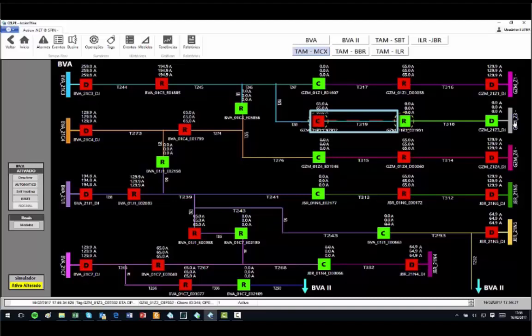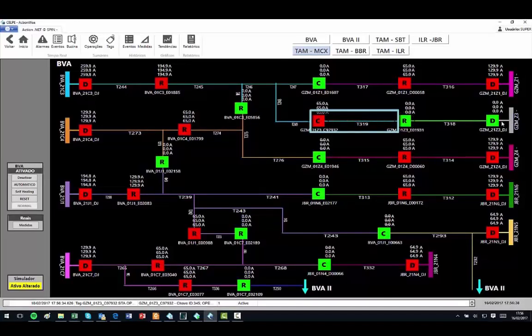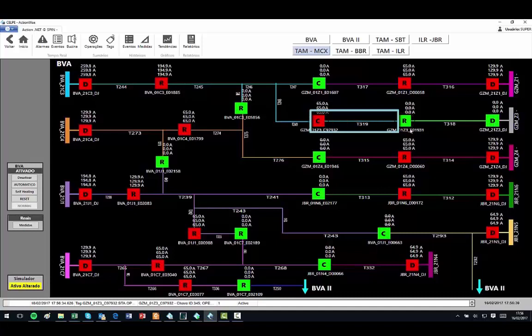The ADMS FLISR module detects the fault and suggests two commands in the maneuvers window, that when executed, isolates the T318 line and re-energizes the T319 line fed by the blue feeder. The switches commanded by the module are highlighted by a yellow circle, and the lines re-energized are highlighted by a red line hatched.